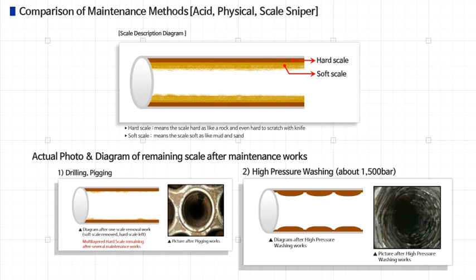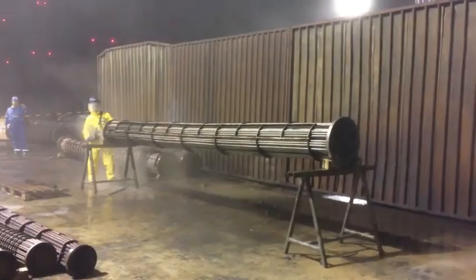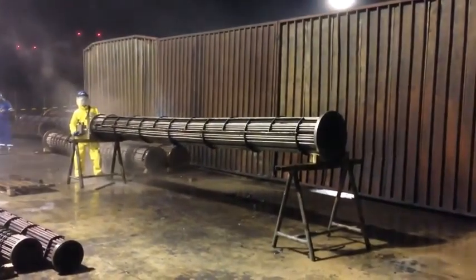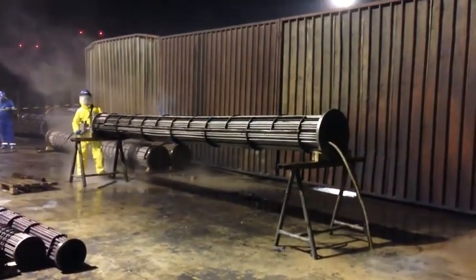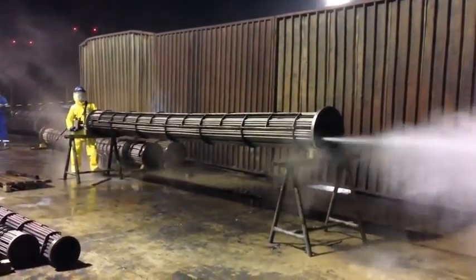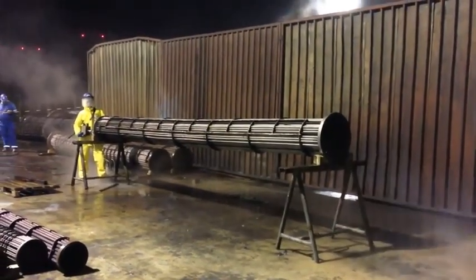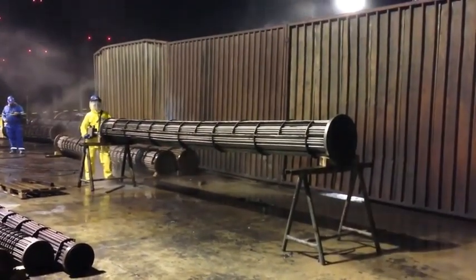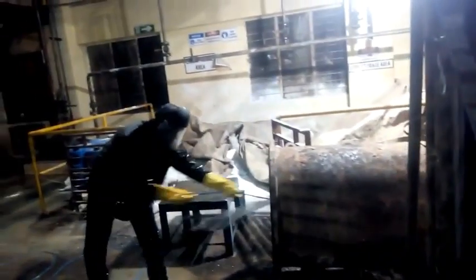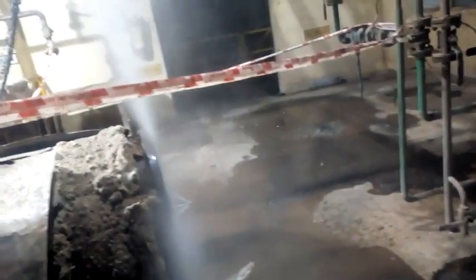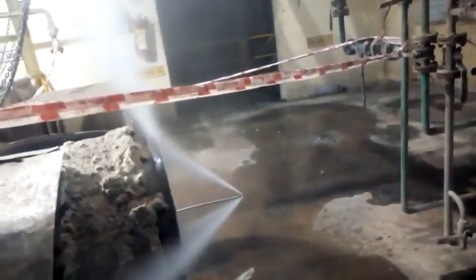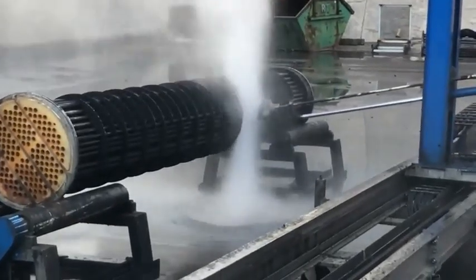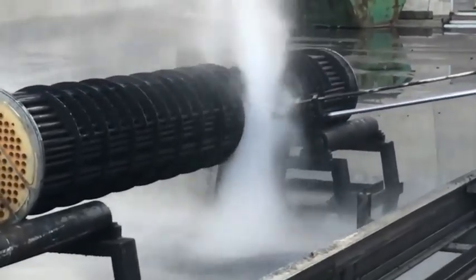Let's see how high pressure washing works. As you can see in the video, soft scale can be removed from the inside of the tube with high pressure water washing, but hard scale is difficult to remove. On the shell side, it is possible to remove scale on parts that come into direct contact with water, but it is difficult to remove scale on inner parts that do not contact with water.